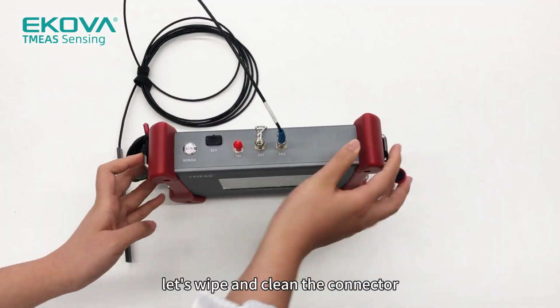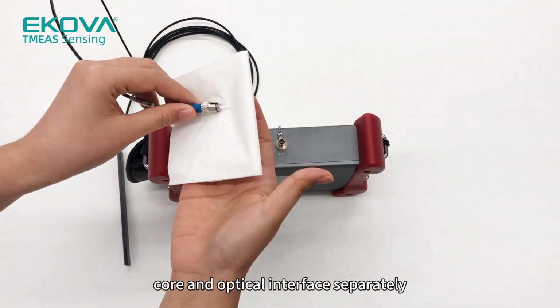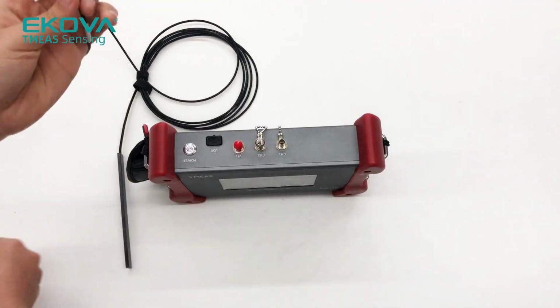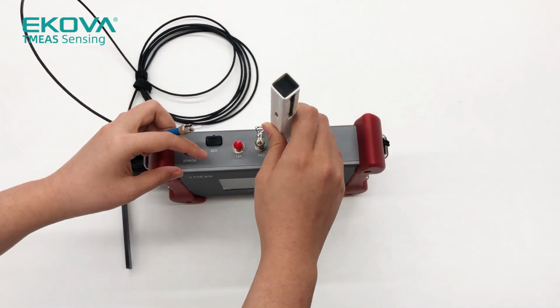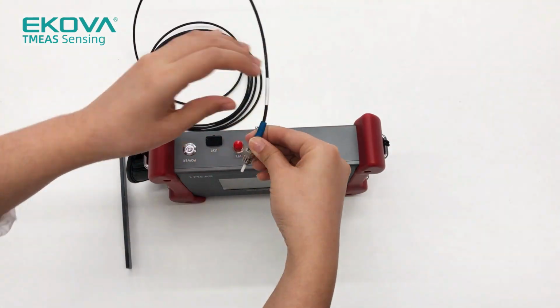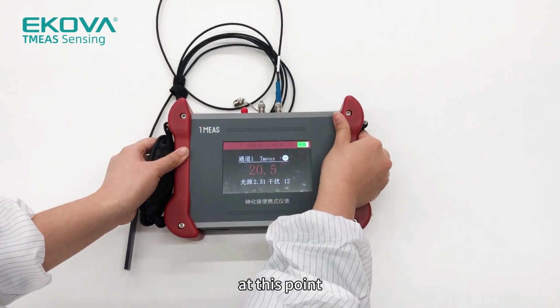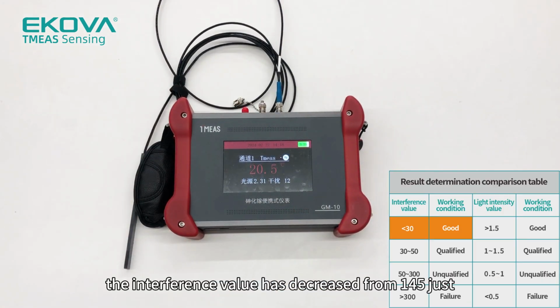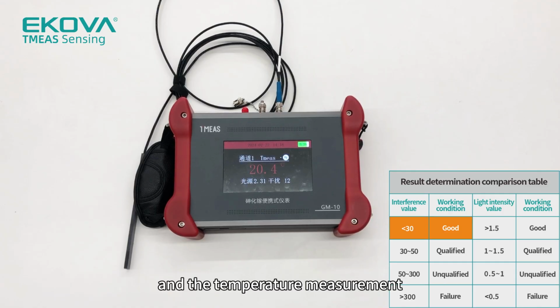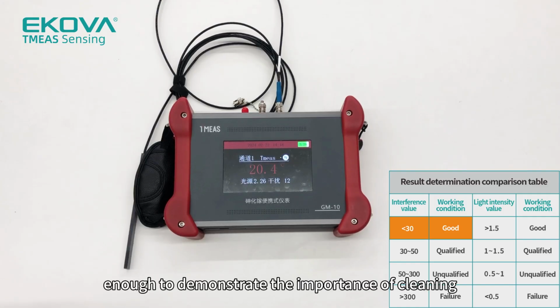Let's wipe and clean the connector core and optical interface separately. And then connect them to take a look. At this point, the interference value has decreased from 145 just now to about 12, and the temperature measurement has returned to a good state, which is enough to demonstrate the importance of cleaning.